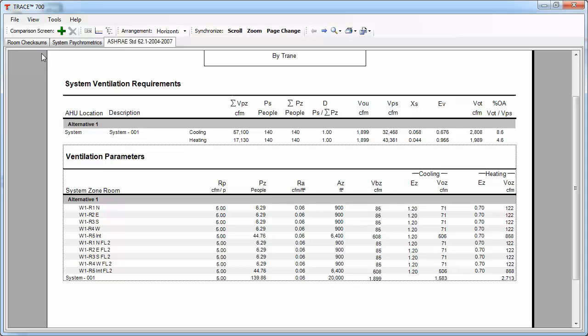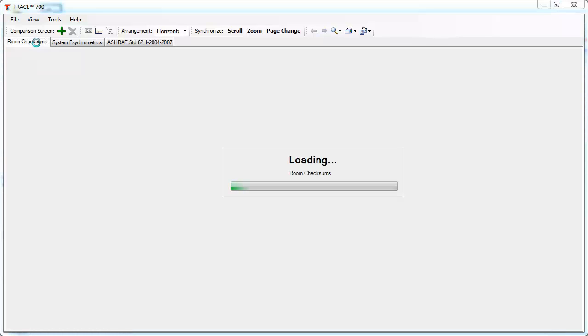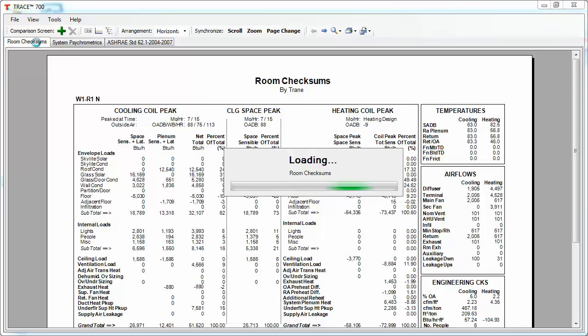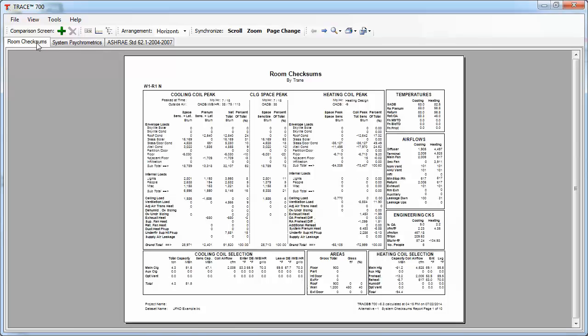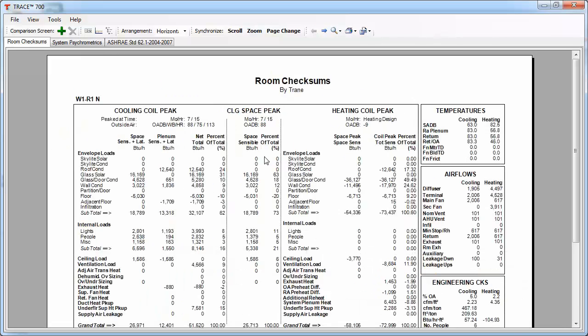Next, we can focus on another report, which is the Checksums Report. I like to take a look at the Room Checksums Report, because then I can focus on it one room at a time, make sure that the loads are being calculated correctly, and that the return air temperatures are being calculated correctly. So, within the space cooling section of the Checksums, which is the center column here, TRACE is going to report the space-sensible values to the occupied layer. So, it's not going to include any loads that go into the unoccupied layer. You're going to notice, then, that some internal gains are not going to equal what you've inputted into the program, and that is because TRACE has already calculated the load to the occupied layer based on the previous calculation methodology that I discussed, and it's going to display this value here.